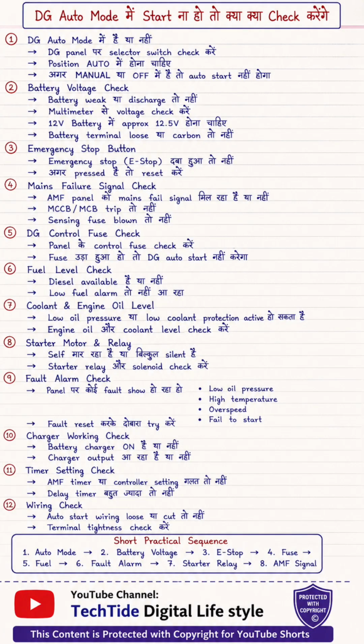If the DG does not start in auto mode, what should you check? Let's understand it step by step in a quick practical way. First, check whether the DG is in auto mode or not. The selector switch on the DG panel should be in auto position. If it is in manual or off mode, the DG will not auto start.